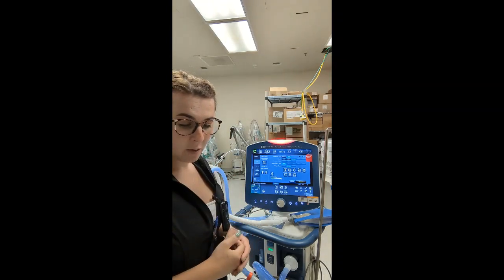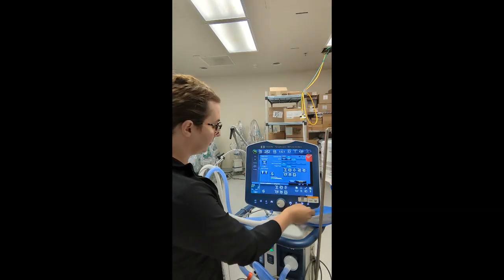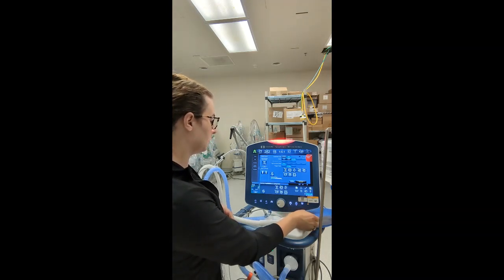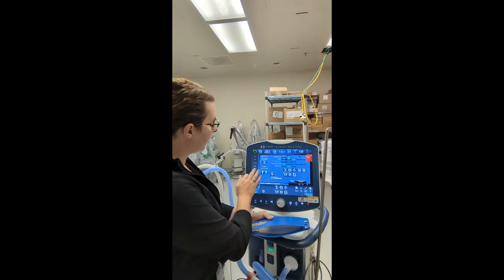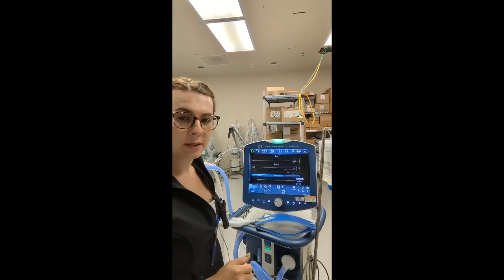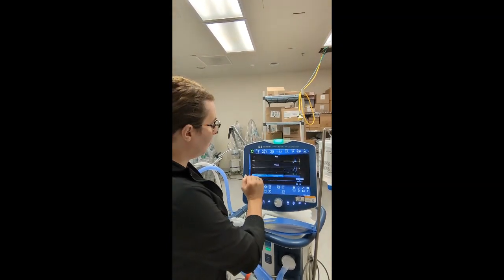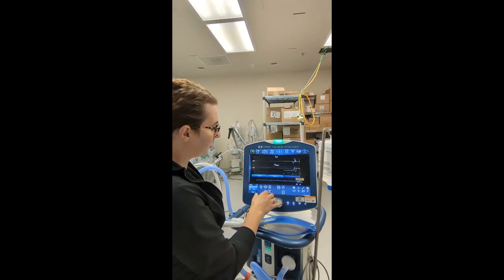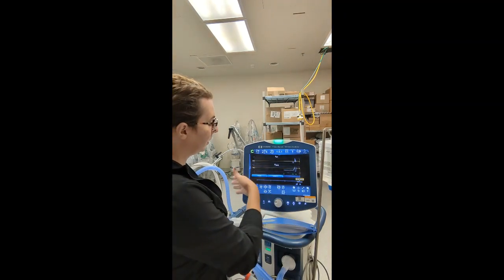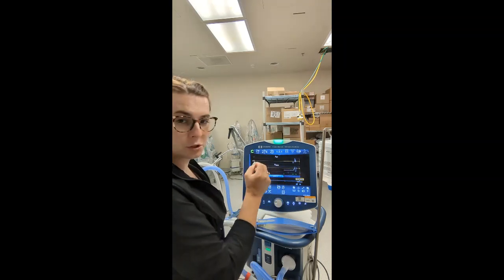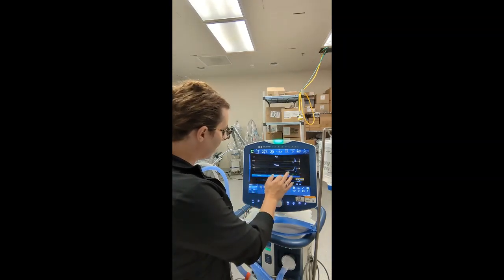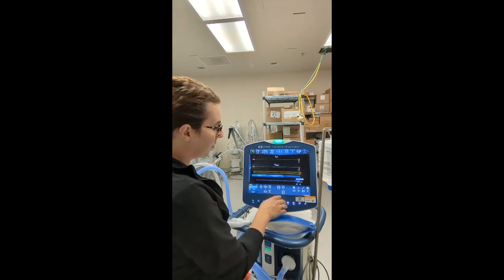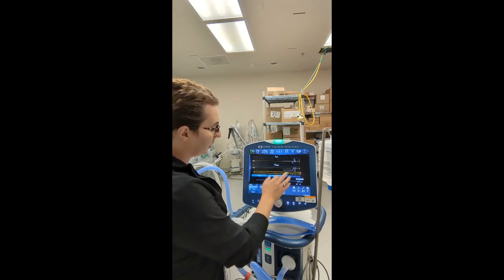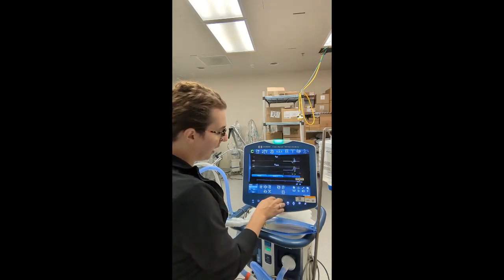I was also asked how to change the trending parameters. When you go to trending, we'll get this screen here on our trends. It depends on how long the ventilator's been running. It'll show a string of information here. If we want to zoom in on a particular area, we click on the time bar at the very bottom of the graph. You'll see some numbers. You click on it. Then you can scroll to widen the shot so you have a longer interval, or scroll in and have a shorter interval. Click again, and then we're able to be more precise on our graph here.